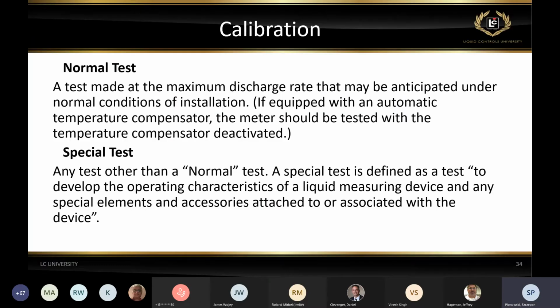Now, in calibration, there are really two types of tests. One is a normal test, which is normally done for accuracy and repeatability at the maximum discharge rate.